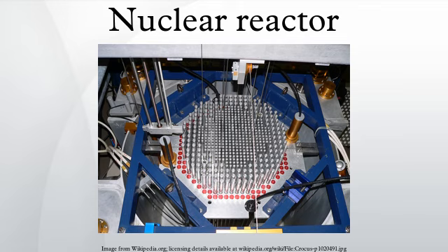In a CANDU reactor, this also allows individual fuel elements to be situated within the reactor core that are best suited to the amount of U-235 in the fuel element. The amount of energy extracted from nuclear fuel is called its burnup, which is expressed in terms of the heat energy produced per initial unit of fuel weight. Burnup is commonly expressed as megawatt-days thermal per metric ton of initial heavy metal.